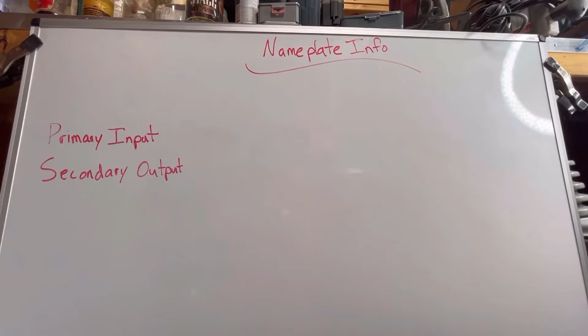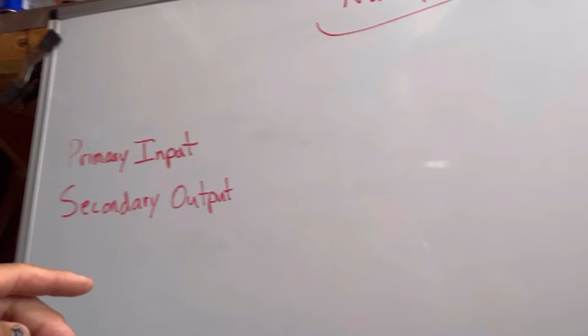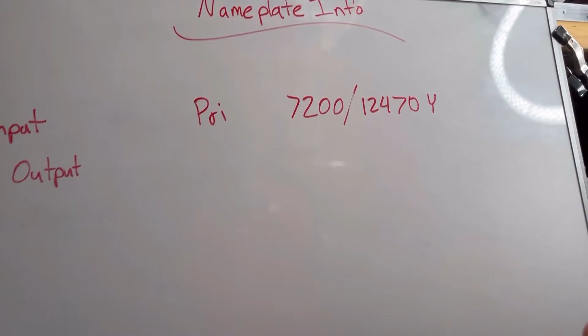All right, guys, so the next thing we're going to talk about is the nameplate information. And specifically, there's a lot of information on a nameplate, like a lot. But really, the only things that we're really concerned with in terms of making the connection is the primary input and the secondary output. So they can give you that information in different ways. So when you're looking on a nameplate, you're going to look for the primary input. So it's going to say primary, and then it'll say something like, for example, sometimes it'll give you two voltages, like 7,200 / 12,470 Y. It'll tell you like that. And what's really important to know about this information and how it gives it to you, this does not tell you how to hook it up Y or delta.